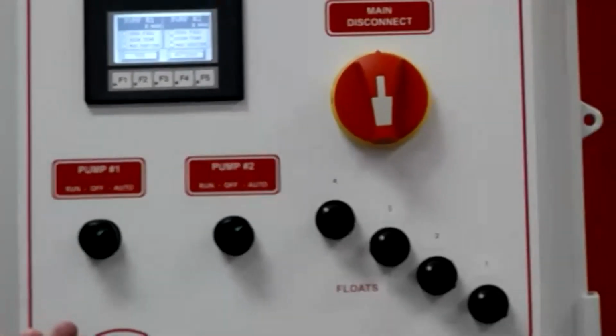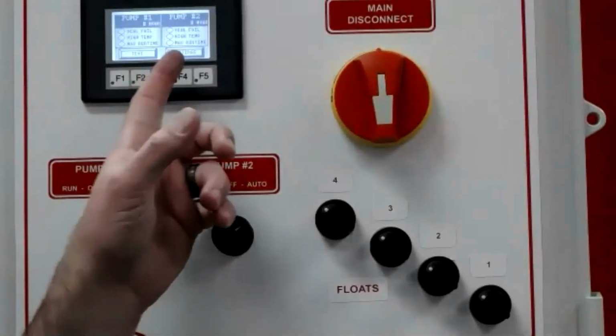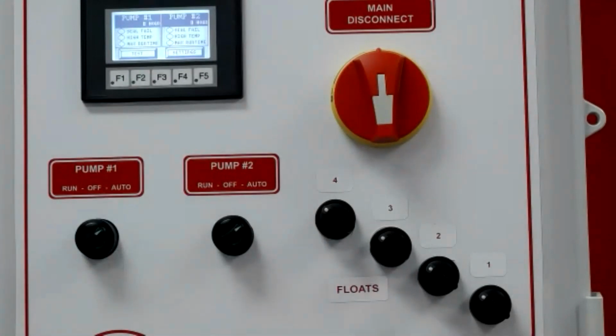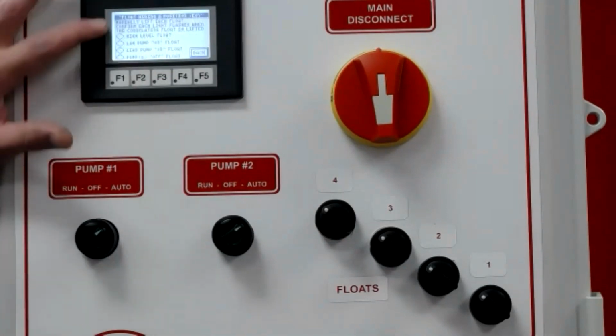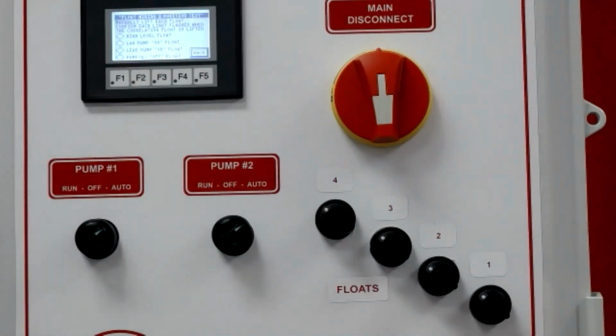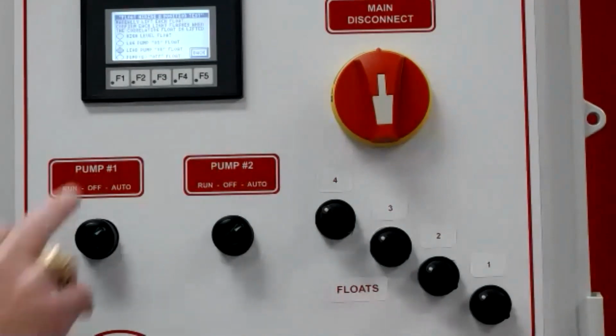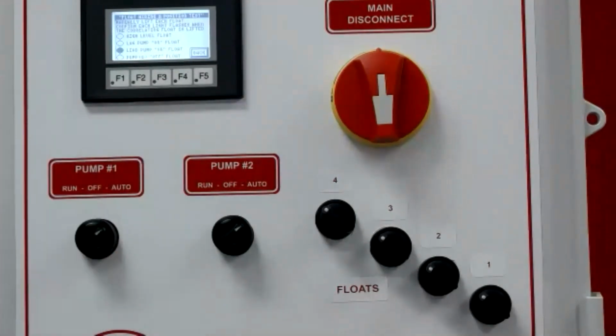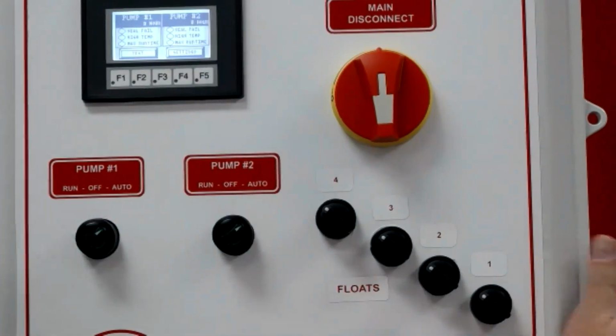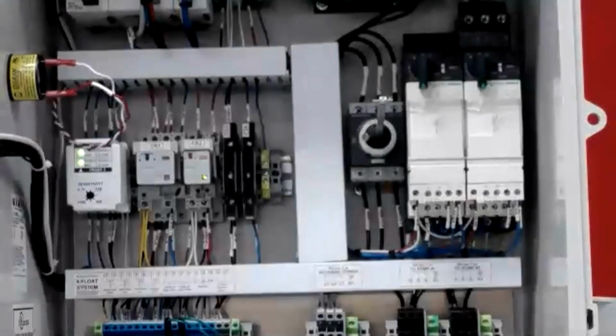This controller can also be used with 2, 3, or 4 floats just by adjusting the settings there. And it also has a float test feature. So you can go in and see what your float switches are. If you flip one of them up, it'll give you some feedback of what float switch you've lifted up and if it's in the correct order, if it's working, things like that. So that's kind of what we've got there. The other thing that's nice on this style here, I'll back out just a little bit.